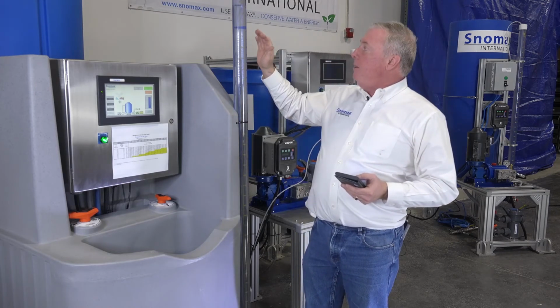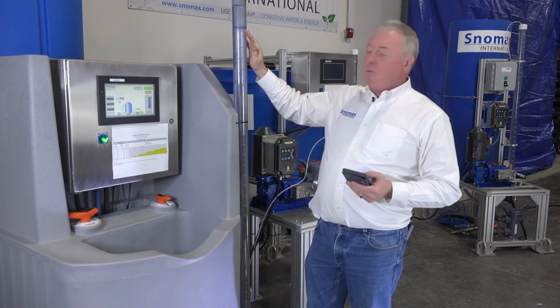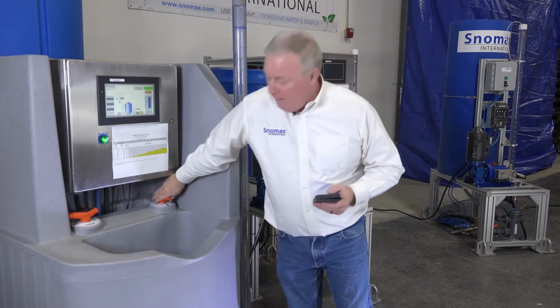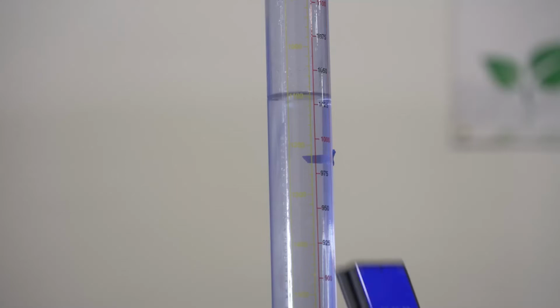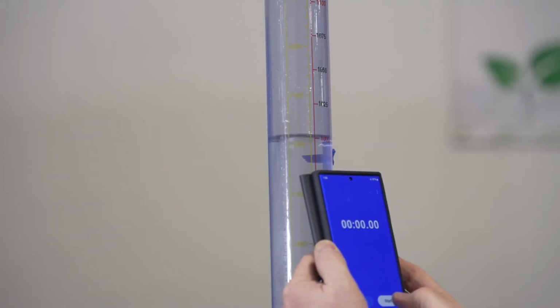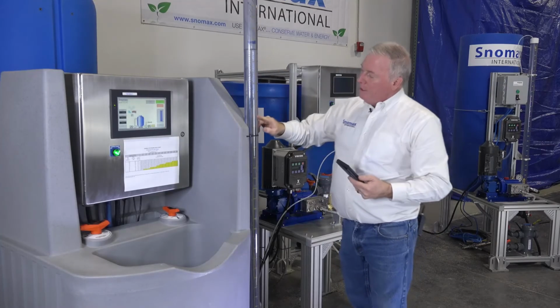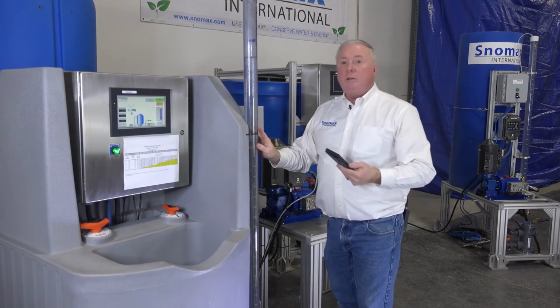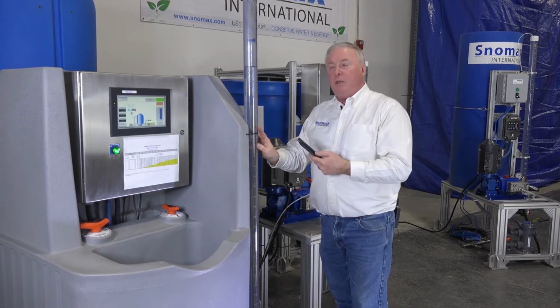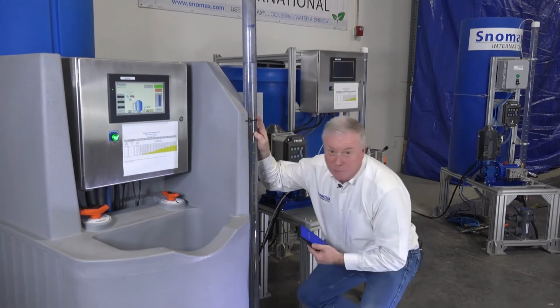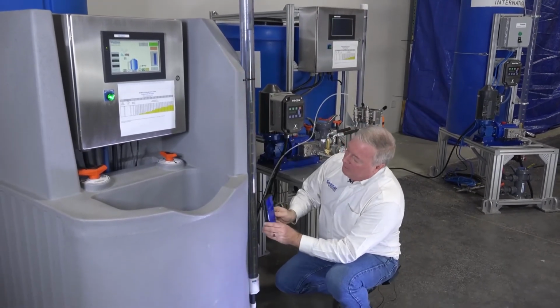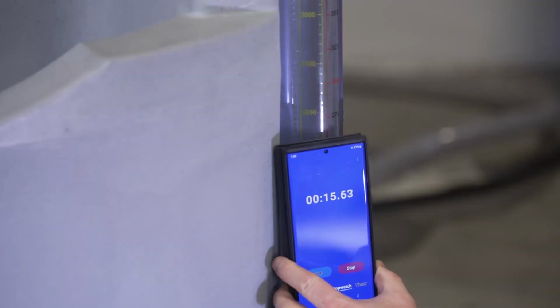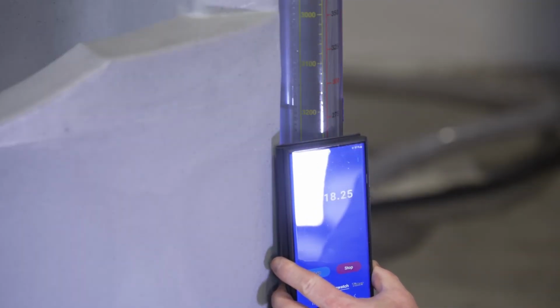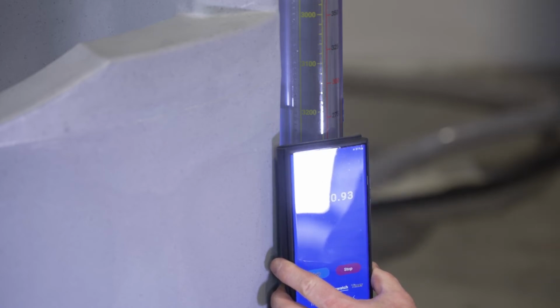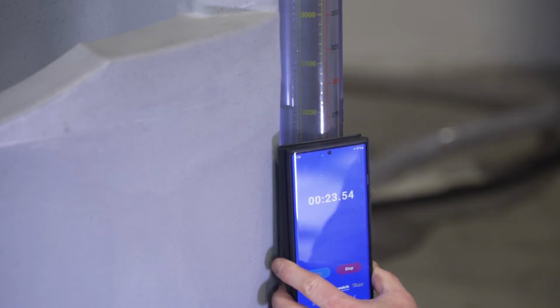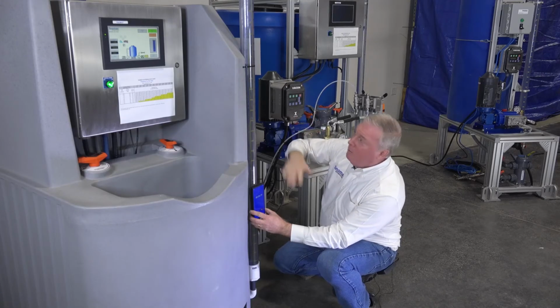So we're going to go up here using the same technique we used on the last one on the calibration column. So I'm going to close this valve. When it hits 1,200 here, I'm going to hit the start button. And we're going to drop this down. And because on the last pump we set it for 2,000 milliliters a minute, we're probably going to hit this pretty close. So I'm going to come down here, and we're trying to hit, since we start at 1,200, so for 2,000 milliliters a minute, we need to hit 3,200 on the scale. And you can pick any point in the scale anywhere you want when you're using it.